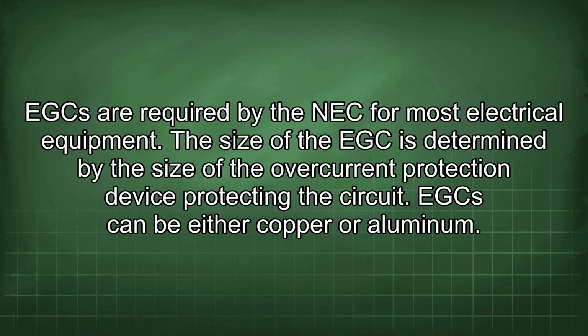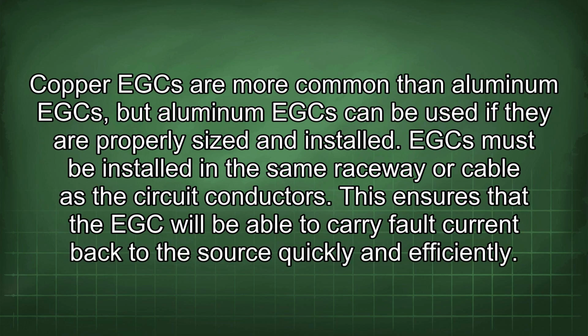EGCs are required by the NEC for most electrical equipment. The size of the EGC is determined by the size of the overcurrent protection device protecting the circuit. EGCs can be either copper or aluminum. Copper EGCs are more common than aluminum EGCs, but aluminum EGCs can be used if they are properly sized and installed. EGCs must be installed in the same raceway or cable as the circuit conductors. This ensures that the EGC will be able to carry fault current back to the source quickly and efficiently.